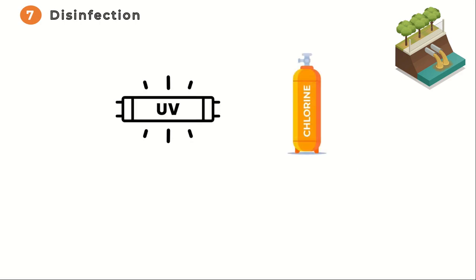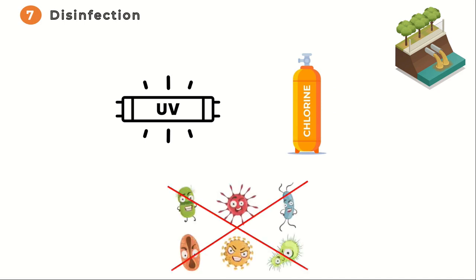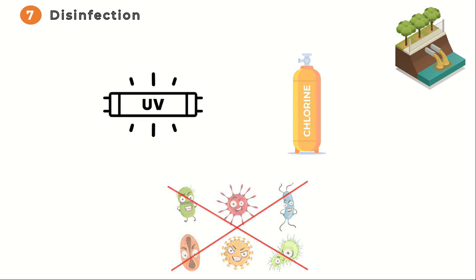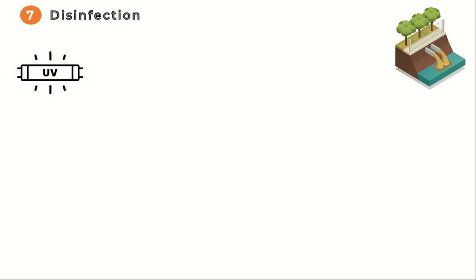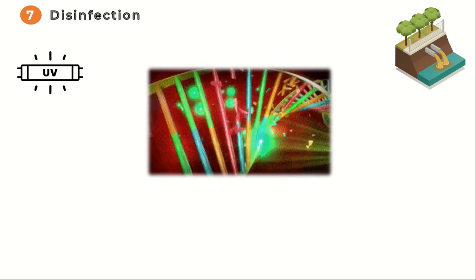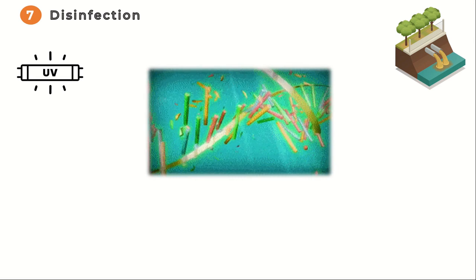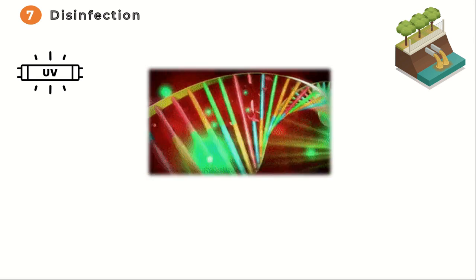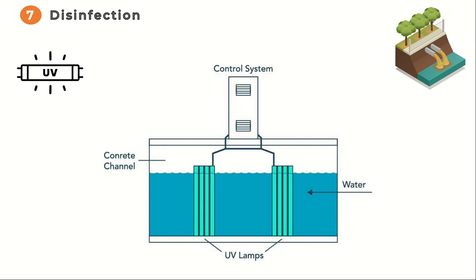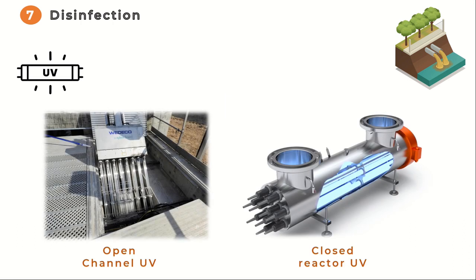The seventh and final step is disinfection. The clarified wastewater is treated with disinfectants such as chlorine or ultraviolet light to kill any remaining harmful microorganisms, ensuring the water is safe to be discharged into the environment. Ultraviolet radiation is produced by low- or medium-pressure mercury vapor lamps with quartz sleeves. The bactericidal role of solar ultraviolet light has the following advantages: shorter time required for pathogen inactivation, absence of byproducts, and a wide range of pathogens targeted.